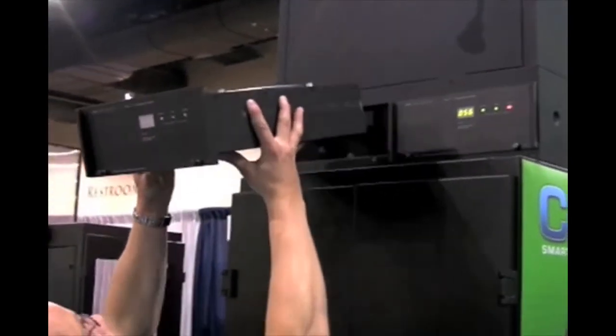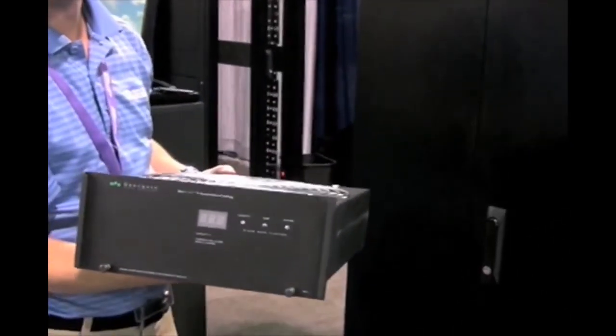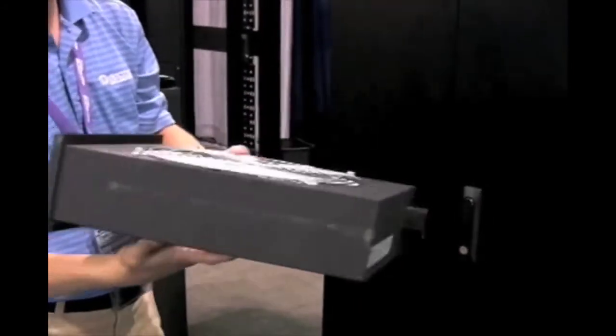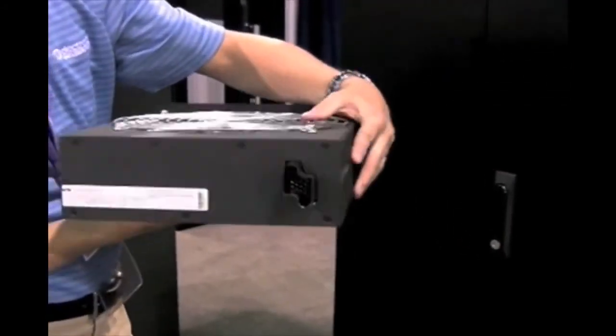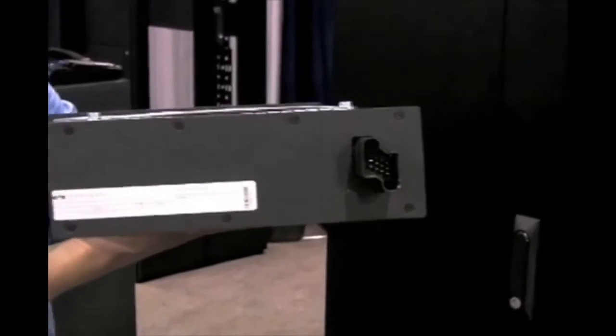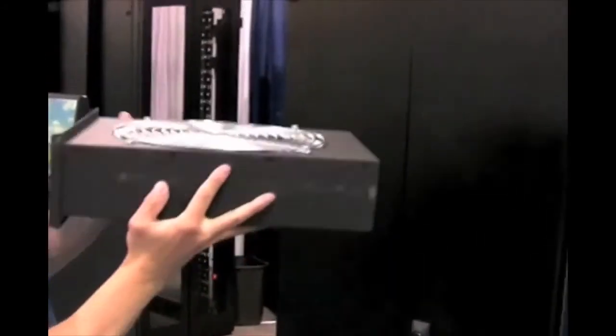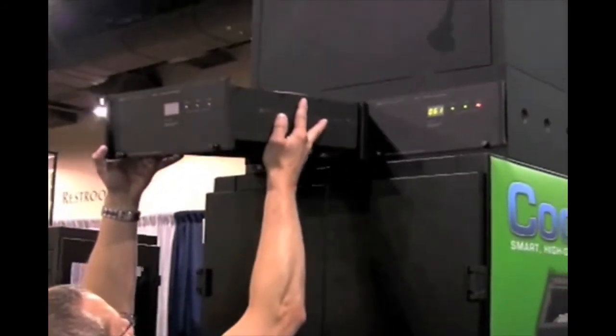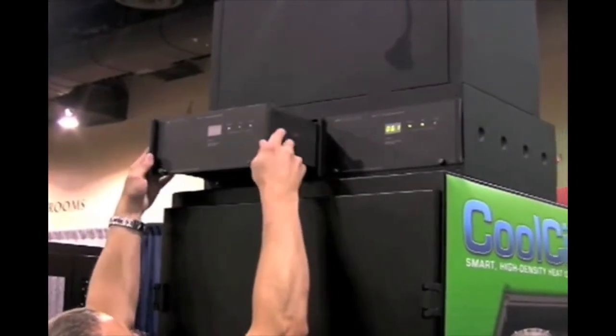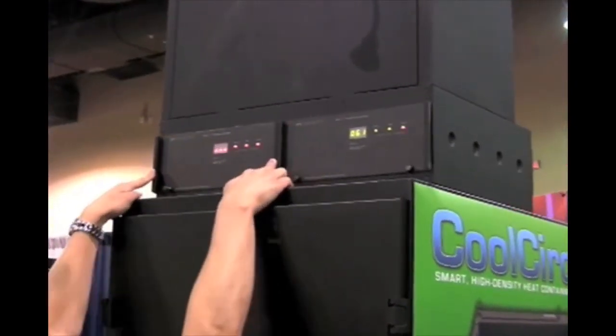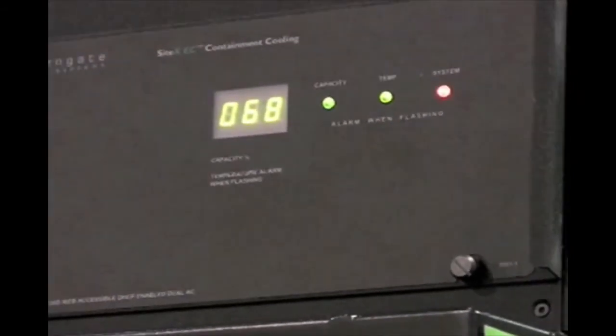With CoolCirc-IT, the two fan modules are fully redundant and hot swappable, and operate at the same speed under normal conditions. However, CoolCirc-IT is an intelligent cooling system, so if a fan fails, the remaining fan module increases its speed automatically to handle the load until another module can be installed. Each fan module has a display showing the current operating capacity. Status indicator lights offer quick visual identification of system operating status.